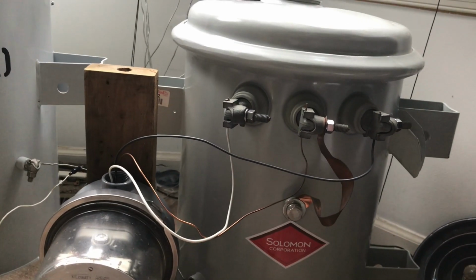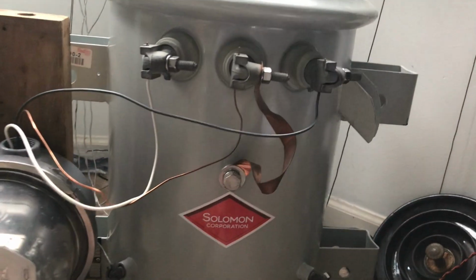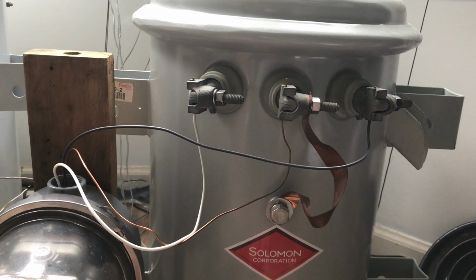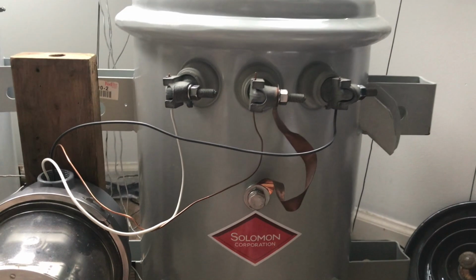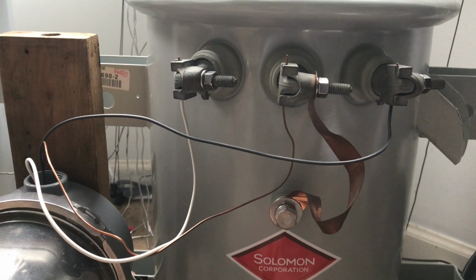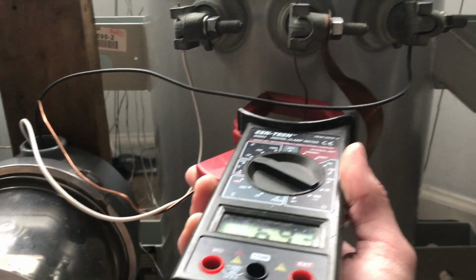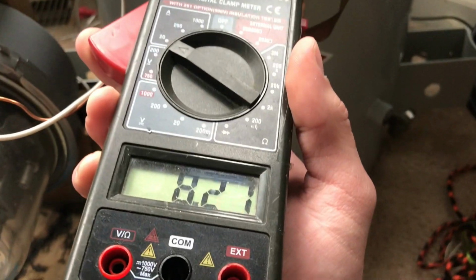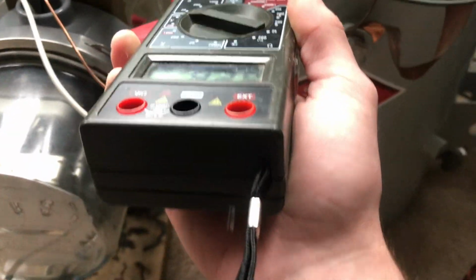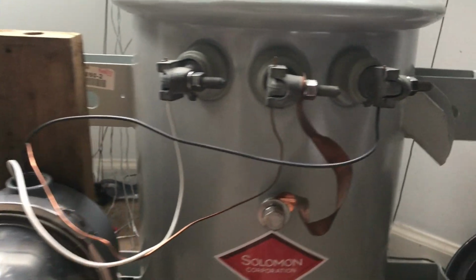So a lot of people say that there's an extreme side that says the neutral is not used at all. It is just for lightning suppression, and there's people who say that it carries back all the current. But as you can see, it's pulling 8 amps. Not the full, not the full 8.4 amps. This is a very inaccurate multimeter, but it's balancing the unbalanced load from both terminals. And if we go to the high voltage side, which I don't advise doing, we could get a measurement on the high voltage ground side.